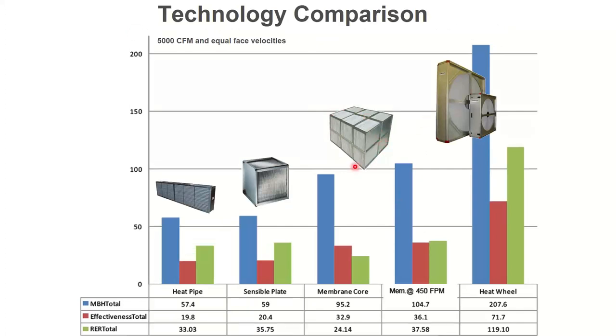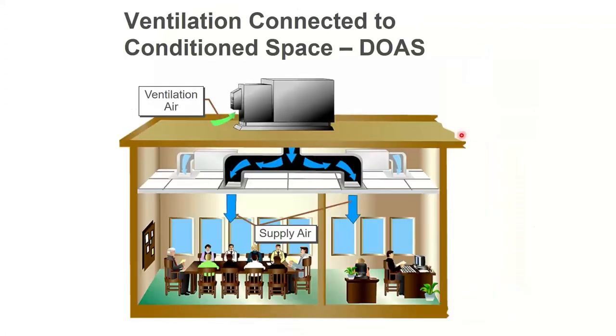But if you have the choice, and we do both, so I'm not biased or anything, if you have the choice, use a wheel style, because you'll be able to do more CFM in a smaller air handler space. More BTUs with a smaller air handler space.